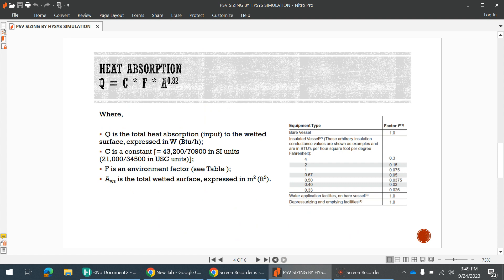Here is the formula for how much heat can be absorbed when fire is around a particular vessel: Q = C × F × A^0.82, where Q is the total heat absorption to the wetted surface expressed in watts (SI unit). C is an empirical constant — it is 43,200 when adequate drainage or firefighting facilities are available, and 70,900 when they are not available. F is the environmental factor.